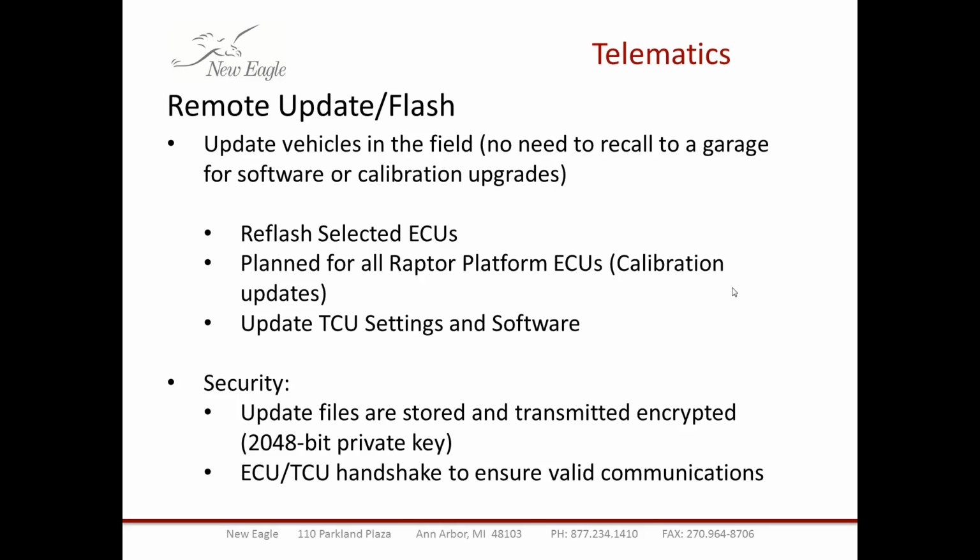And so we need to be very careful about when an update is applied, because the control application will not be running at that time. So what Scott's going to describe is the Safe to Update protocol, which is a piece that goes both in the embedded side and in the telematics unit that assures that it's safe to update.